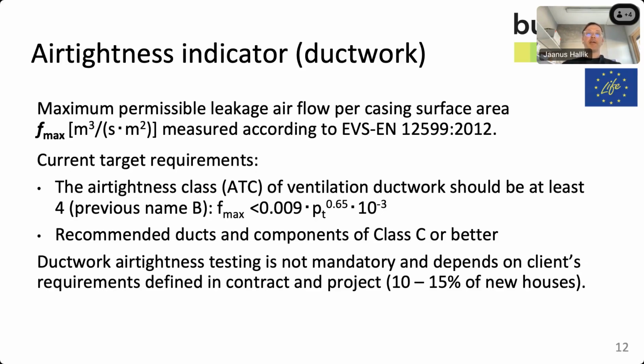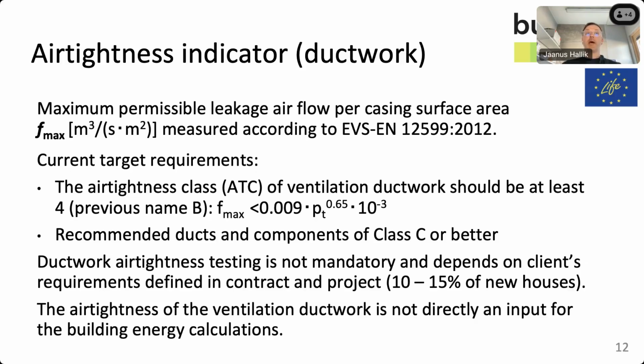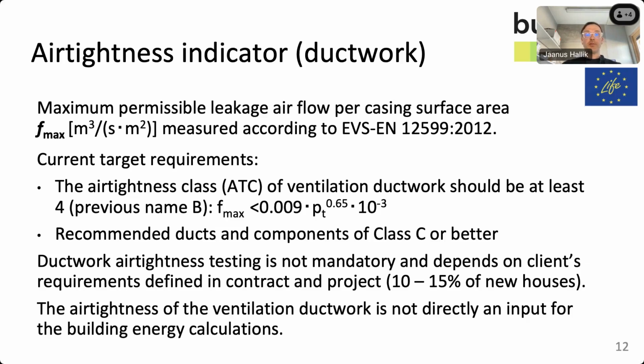If it's for some specific buildings, like hospitals, clean rooms, or large cold storage houses, there's a specific, stricter level agreed in the contract. But usually it's just the default, and usually 10 to 15% of new houses measure the airtightness of the ductwork. And as of now, the airtightness of the ventilation duct is not directly an input for the building energy calculations and the energy performance certification. So it's not a very hard criterion, unfortunately, for this part.